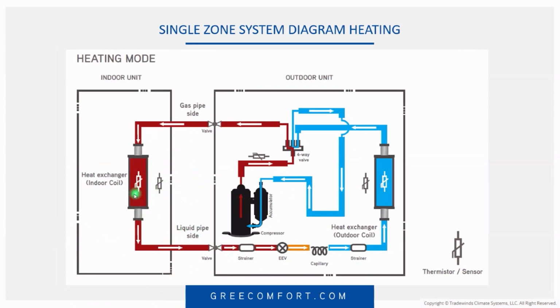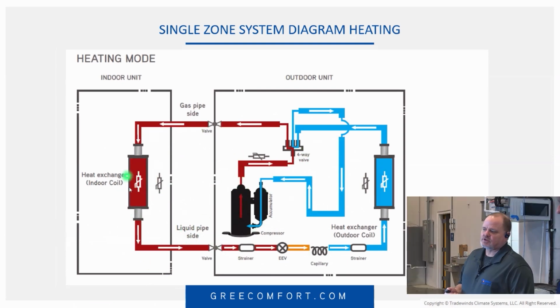So that gets interpreted and sent back to the main board in the outdoor unit. The outdoor unit says, okay, I've got a 10-degree demand, I've got to try to get the temperature up in that space. So what it also does is help adjust the speed of the compressor, by controlling the hertz speed of that compressor. And as we ramp that up more, it's watching this coil temperature in here.